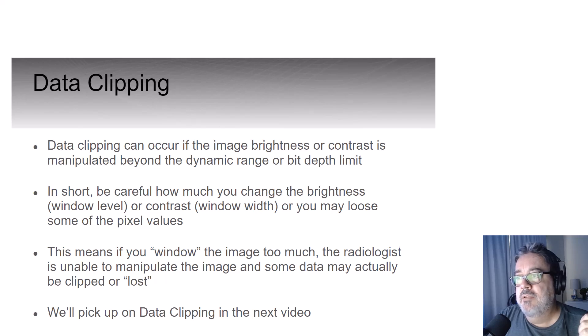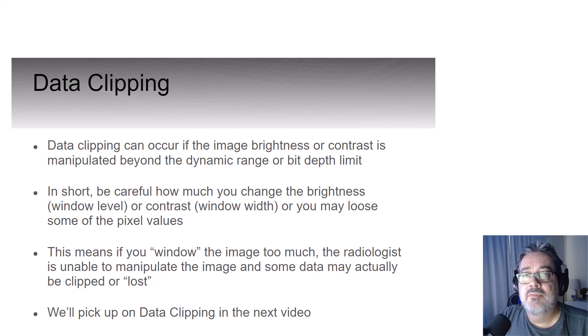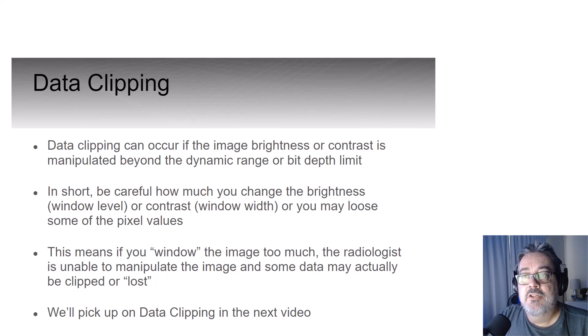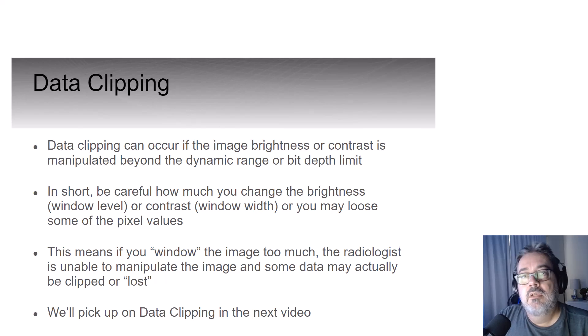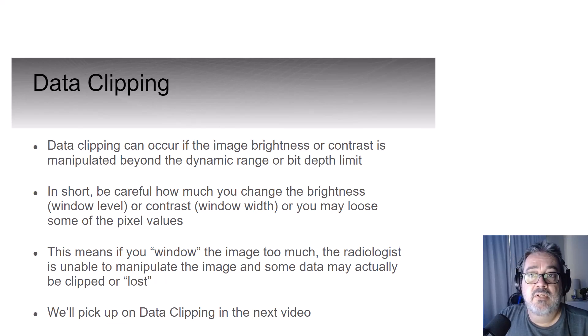I'm going to briefly touch on data clipping. Data clipping is what happens when you manipulate the window width and/or window level — the brightness and contrast — beyond the dynamic range or bit depth limit of that system. When you adjust brightness and contrast at the technologist control panel before it's sent to the radiologist, you're essentially limiting the data you're sending them for interpretation. Adjusting the control panel is only meant to QC your images — never use it to make your image look more presentable before sending it to PACS. If you use it at all, just reset it to its original state before you send it over.